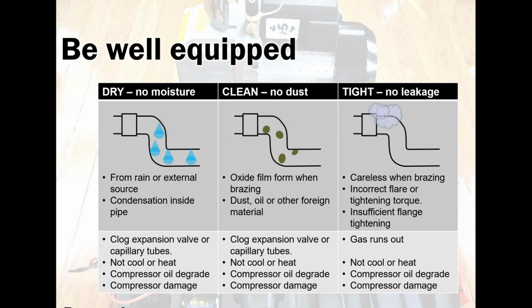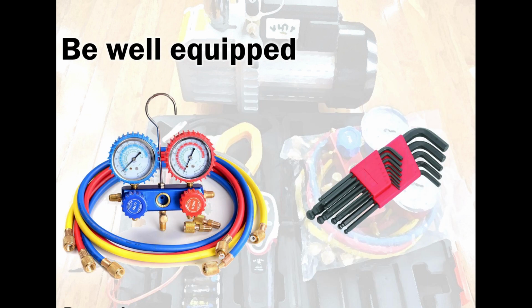And always remember to replace the oil in your vacuum pump. Always remember, guys, do not use the same oil. Just like your car, every 5,000 kilometers, we use kilometers here, depending on the model and the age of the car, you change oil. Same with the compressor oil. Same with the vacuum pump oil. Always change that oil for good vacuuming, for good micron achievement.